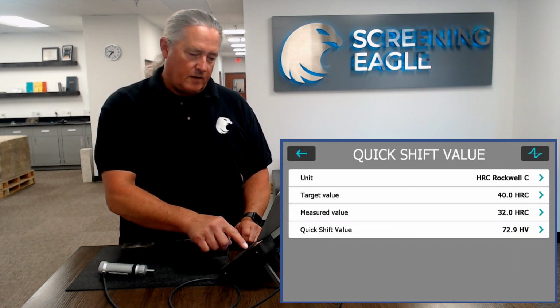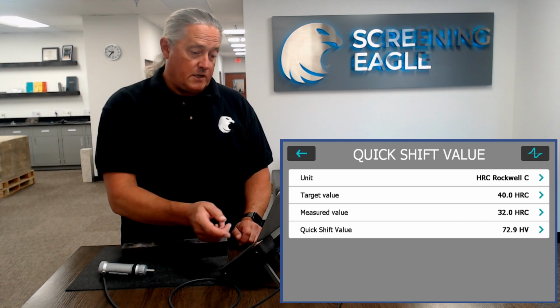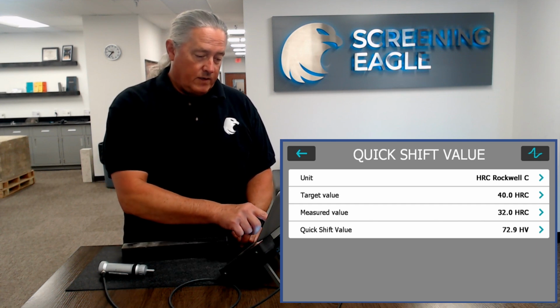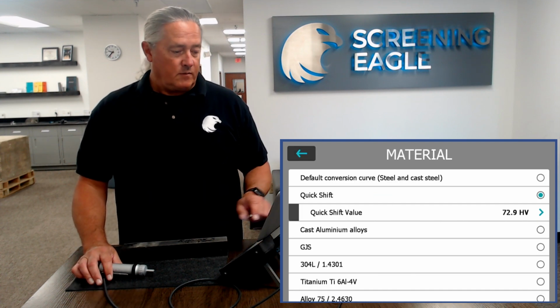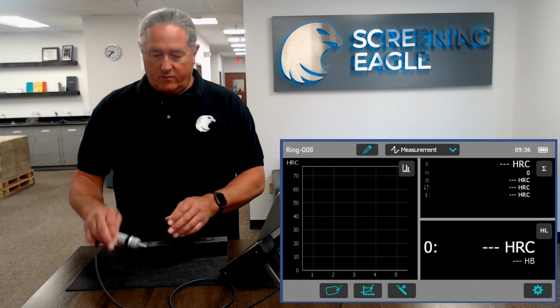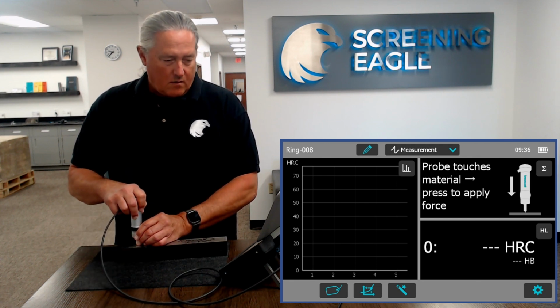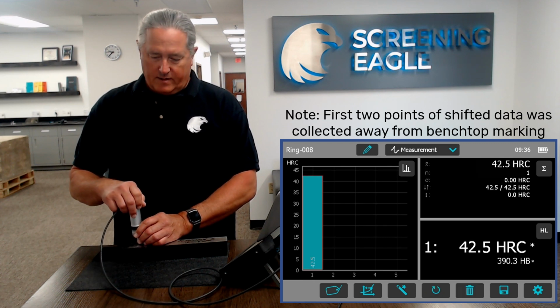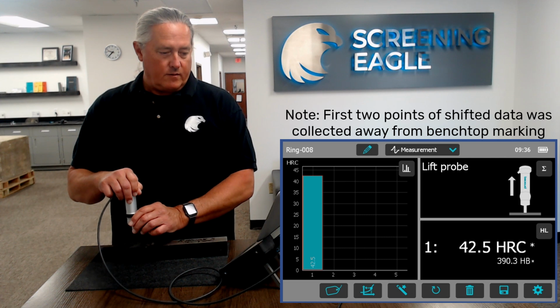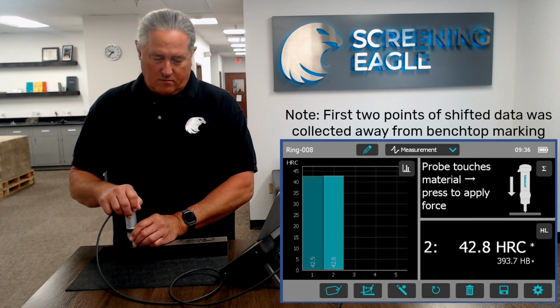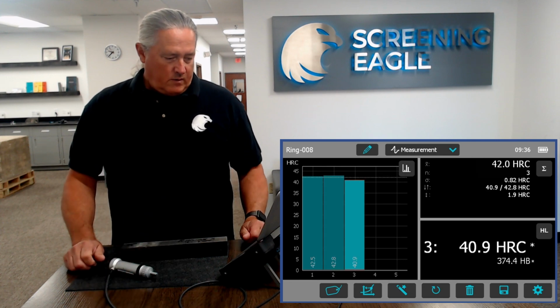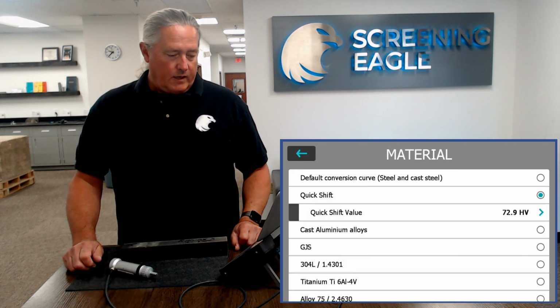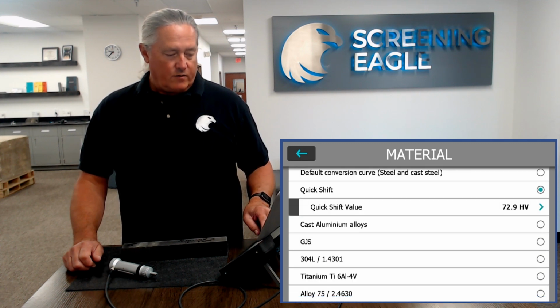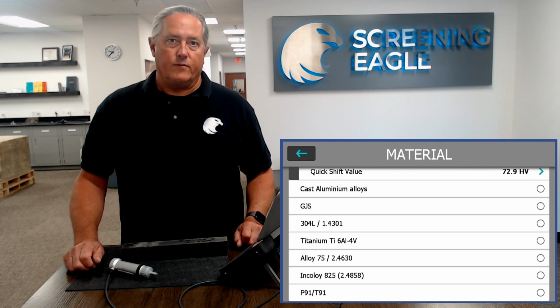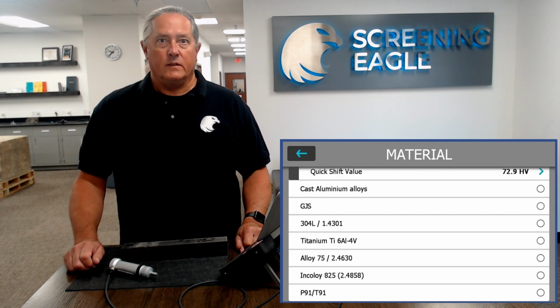And now you can see it's automatically calculated a 72.9 HV shift. But we don't worry about that. We do the shift in HV because that's the native scale of the Equotip UCI. So now when we go back to our measuring screen, we can get readings that are within the calibrated range. And so again, if your material doesn't fit in the default conversion or fit any of these other materials that we have preloaded in, use the quick shift and it'll get you back within calibration for that material that you're testing.